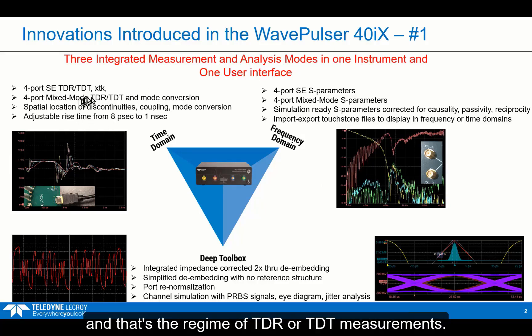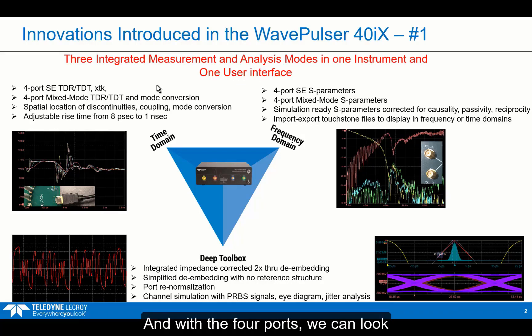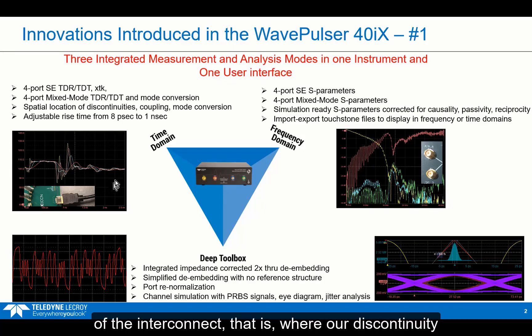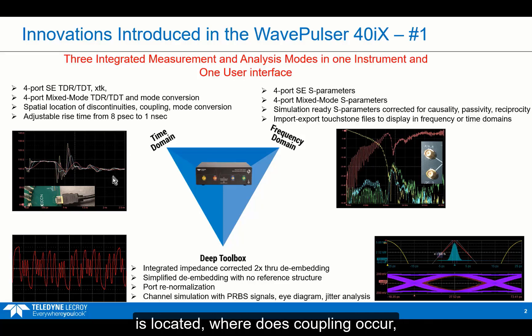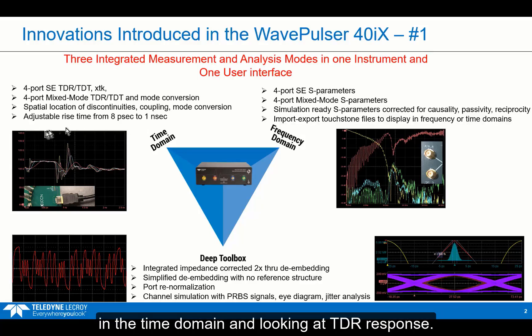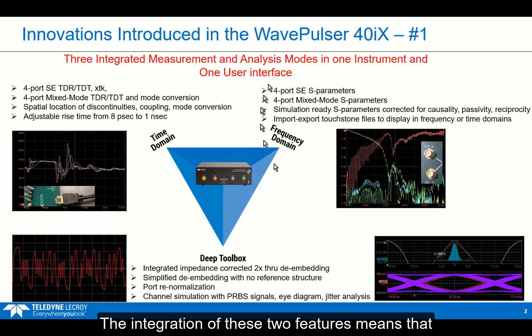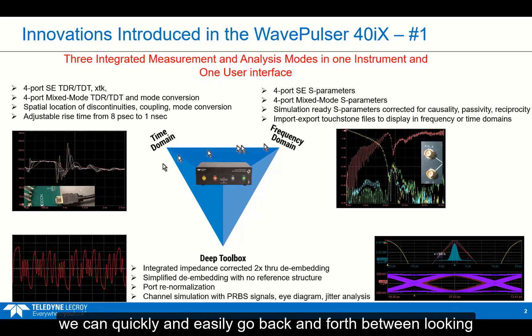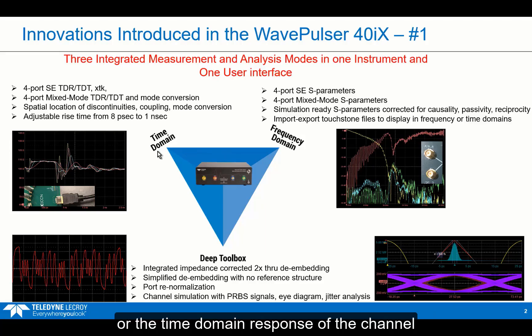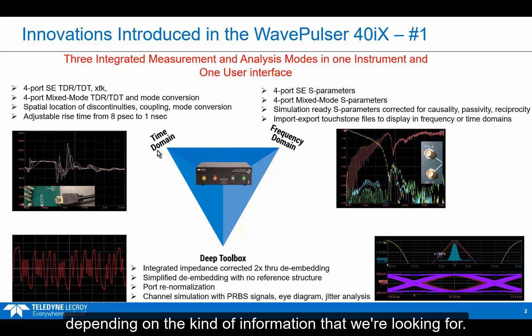That's the regime of TDR or TDT measurements. With four ports, we can look at the TDR or TDT response either as single-ended or as mixed-mode. Whenever we care about spatial information of the interconnect — where are discontinuities located, where does coupling occur, where does mode conversion occur — we always want to be thinking about displaying the data in the time domain and looking at TDR response. The integration of these two features means that we can quickly and easily go back and forth between the frequency domain and time domain response of our channel.